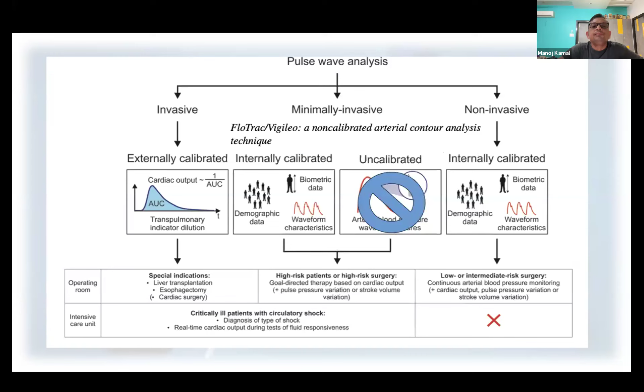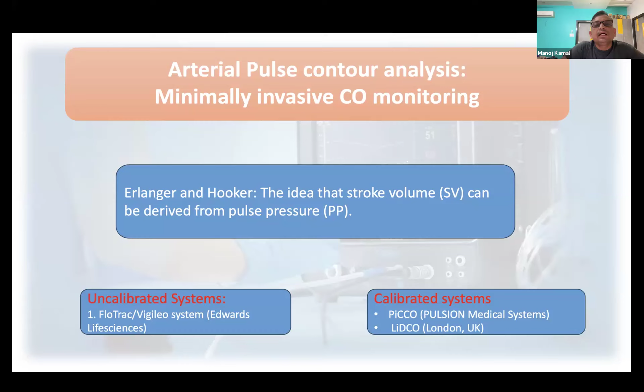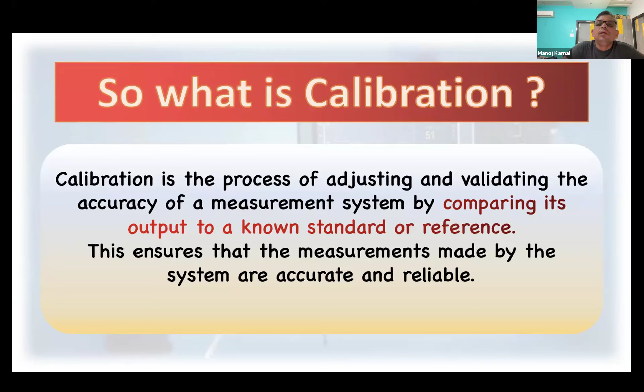And we are discussing calibrated methods. FloTrac and Vigileo are non-calibrated arterial pulse contour analysis techniques. Erlanger and Hooker had the idea that stroke volume can be derived from change in the pulse pressure. So by using this principle, we use the method to measure the cardiac output. Another thing is, what is calibration? Calibration is the process of adjusting and validating the accuracy of a measurement system by comparing its output to a standard or reference. This ensures the measurements made by the system are accurate and reliable. Hence, calibrated systems are more reliable for high-risk surgery.